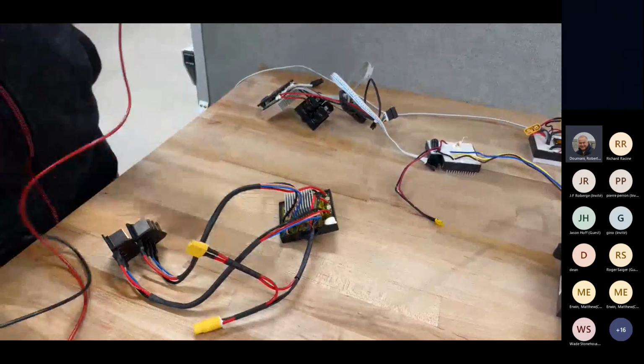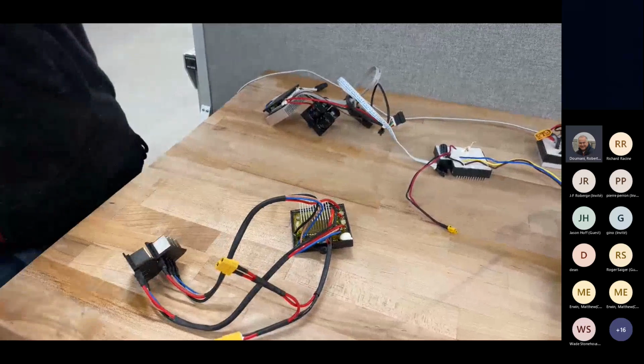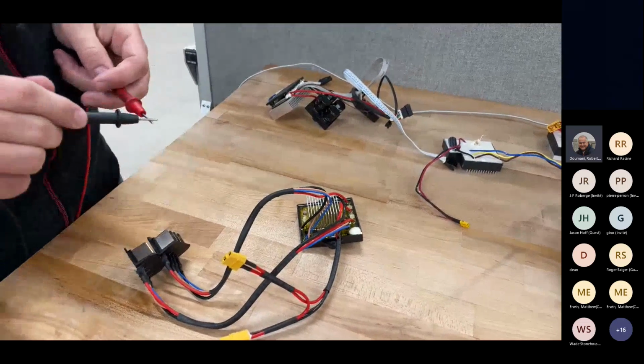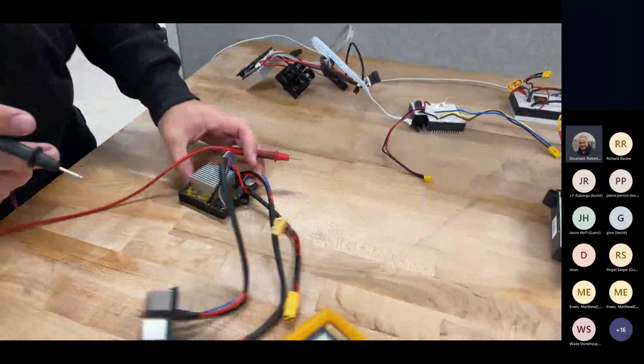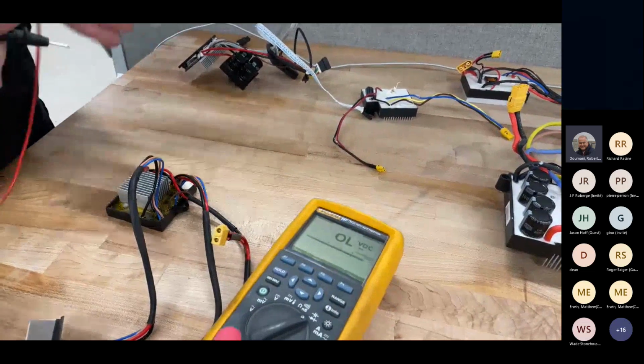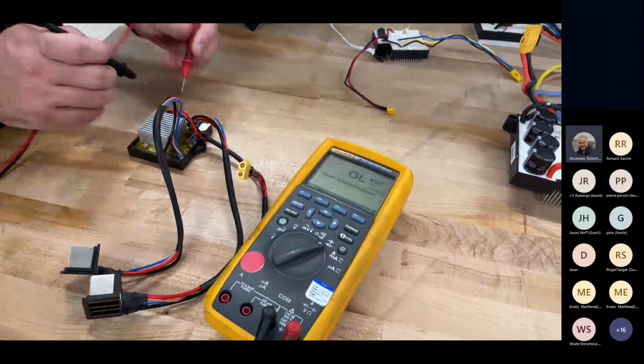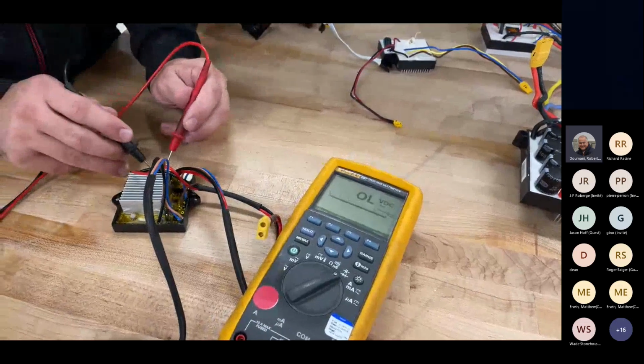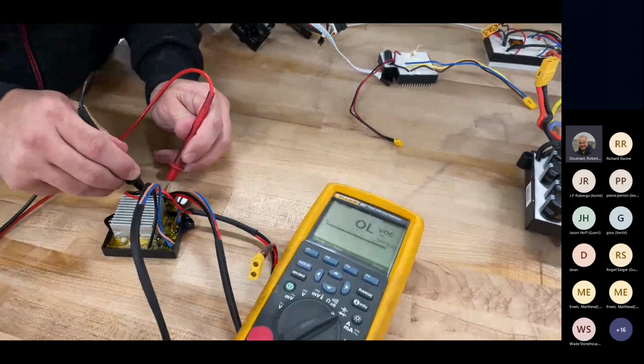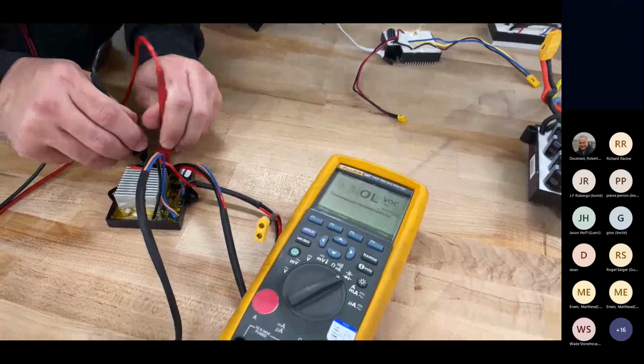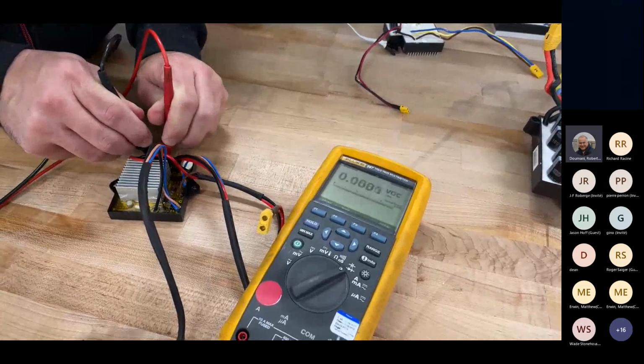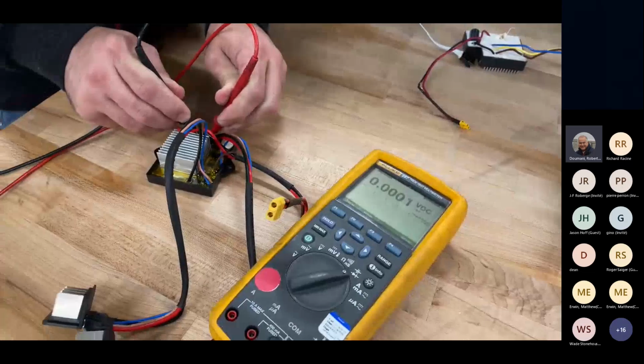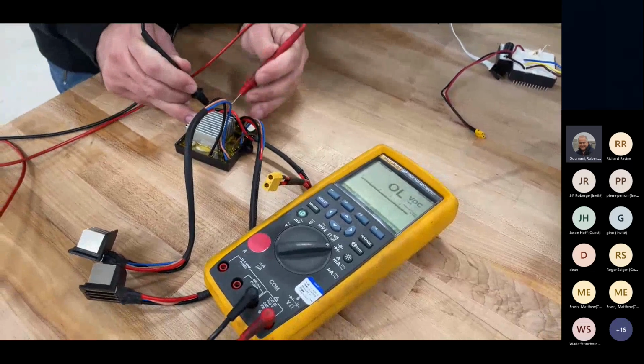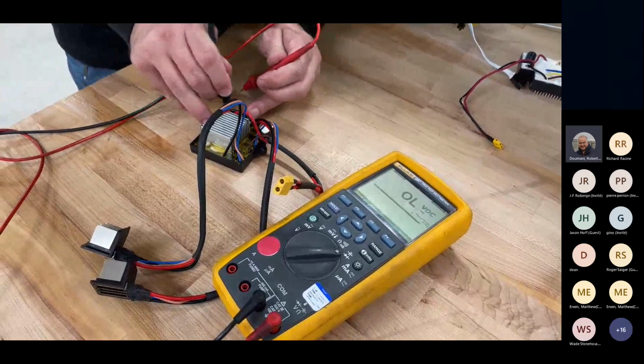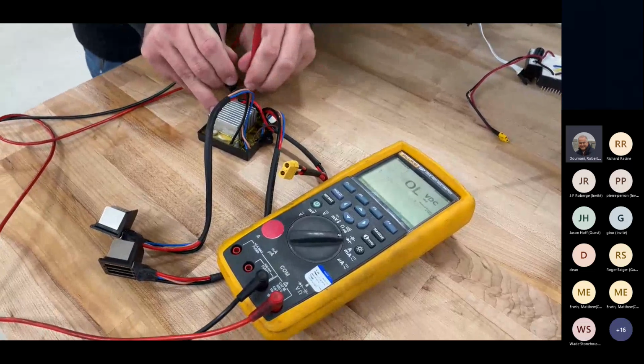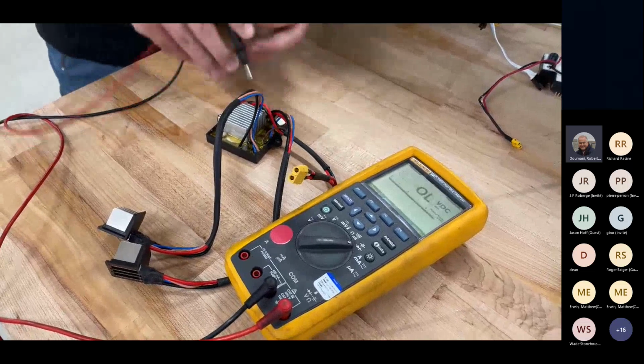To test those fuses, you're just looking for continuity across them. Put your meter into whichever mode shows continuity, on mine that's diode mode. You're going to pierce across the two here, through the rubber until you get a good beep. That one's good, and there's one for each, pierce next to it here, so we know both of those are good.